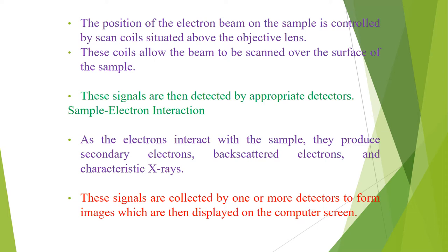In the sample-electron interaction, the scanning electron microscope produces images by scanning the sample with a high-energy beam of electrons. As the electrons interact with the sample, they produce secondary electrons, backscattered electrons, and characteristic X-rays. These signals are collected by one or more detectors to form images, which are then displayed on the computer screen.